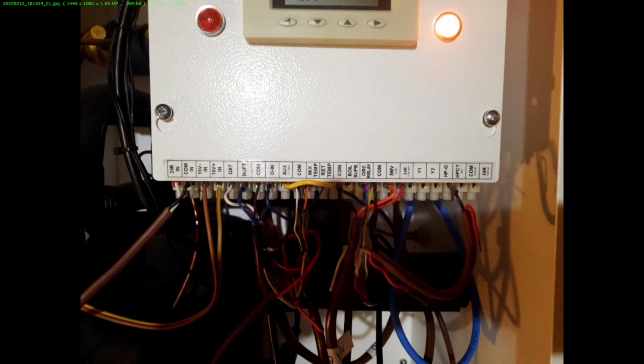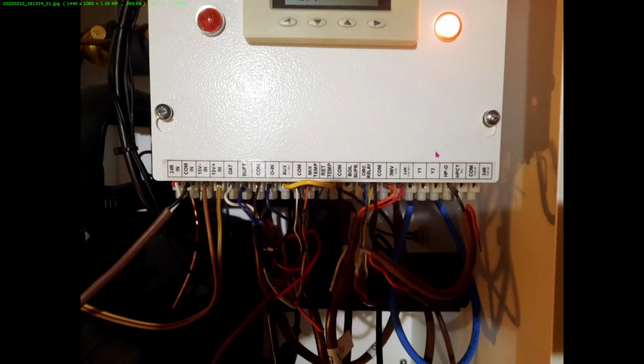We have control for an auxiliary heating supply if required, or a backup heating supply if required. We do not have one. We felt we didn't need one on this project. And then it has all of the controls for the heat pump, both inputs and outputs. And then finally, it has the control for the three-way mixing valve.